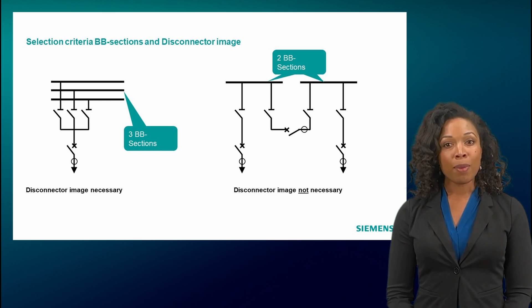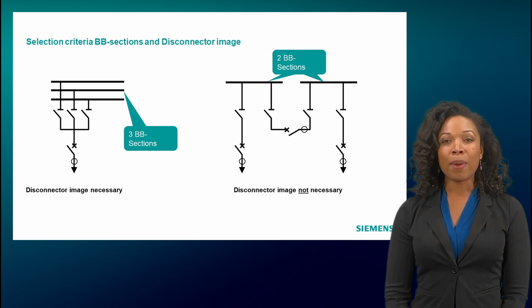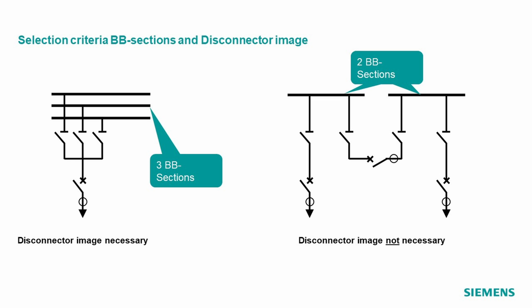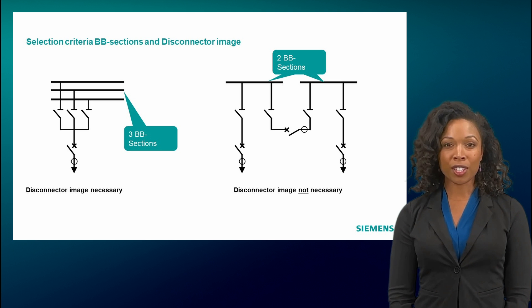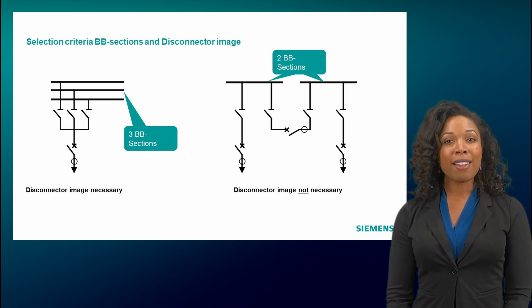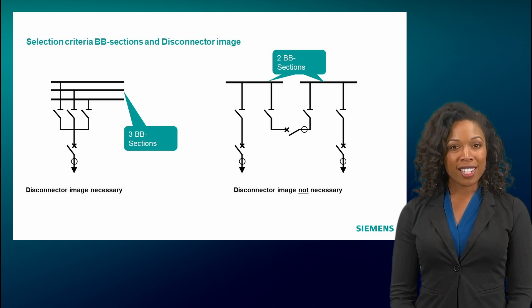When defining the basic properties, it is necessary to specify the number of maximum busbar sections. Furthermore, it must be determined whether the disconnector replica is required. The picture on the left shows a triple busbar. Since the current flows to the first, second, or third busbar section depending on the disconnector position, the protection system needs the disconnector image to know which busbar or node the measured value must be attributed to. In the figure on the right, the recorded current value can only be attributed to one busbar section at a time, so the disconnector replica is not required. Since the two busbar sections are connected via a measured longitudinal coupling, each busbar half can be calculated separately, and two busbar sections are required.